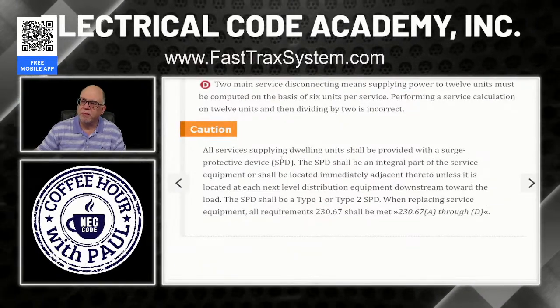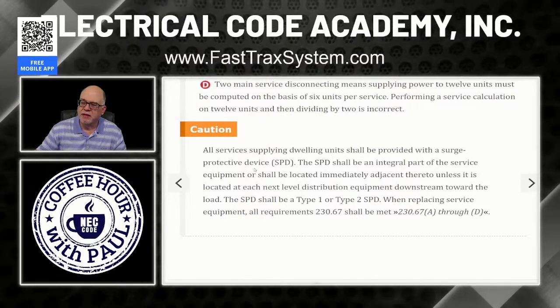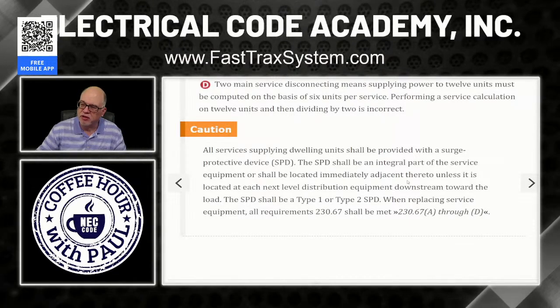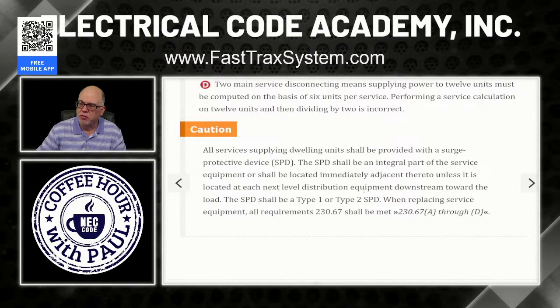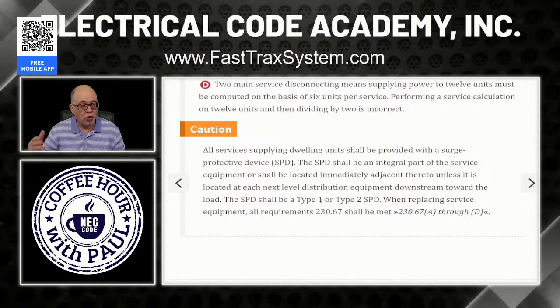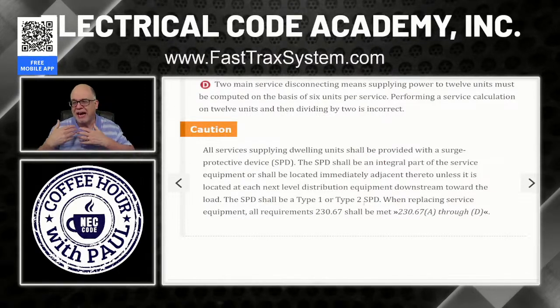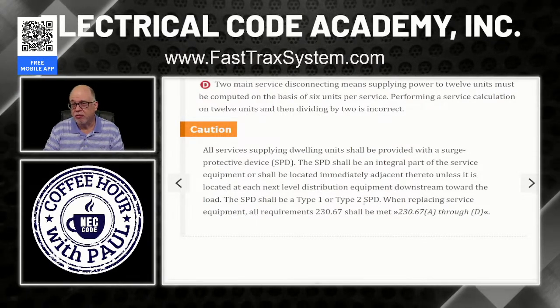Now, all services supplying dwelling units shall be provided with a surge protective device, SPD. The SPD shall be an integral part of the service equipment or shall be located immediately adjacent thereto, unless it is located at each next level distribution equipment downstream toward the load. Okay, so the SPD shall be a type 1 or a type 2. And also, if there's a retrofit or remodel and you replace the service, then you have to install SPDs. Now it's a requirement, right?